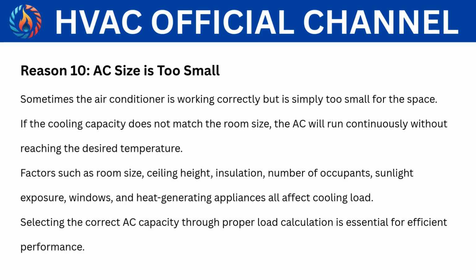Reason 10. AC size is too small. Sometimes the air conditioner is working correctly but is simply too small for the space. If the cooling capacity does not match the room size, the AC will run continuously without reaching the desired temperature. Factors such as room size, ceiling height, insulation, number of occupants, sunlight exposure, windows, and heat-generating appliances all affect cooling load. Selecting the correct AC capacity through proper load calculation is essential for efficient performance.